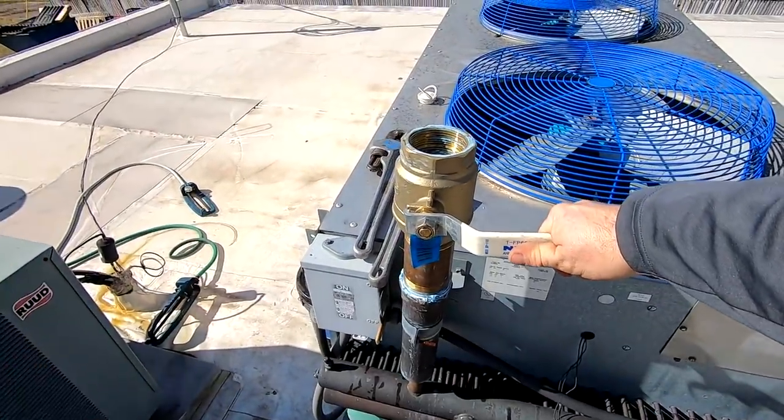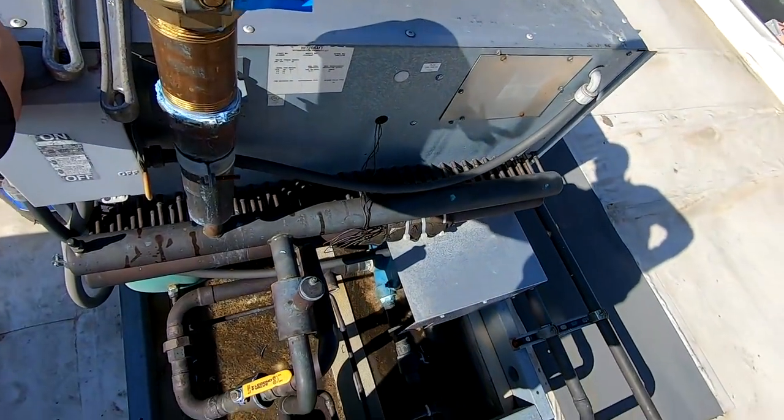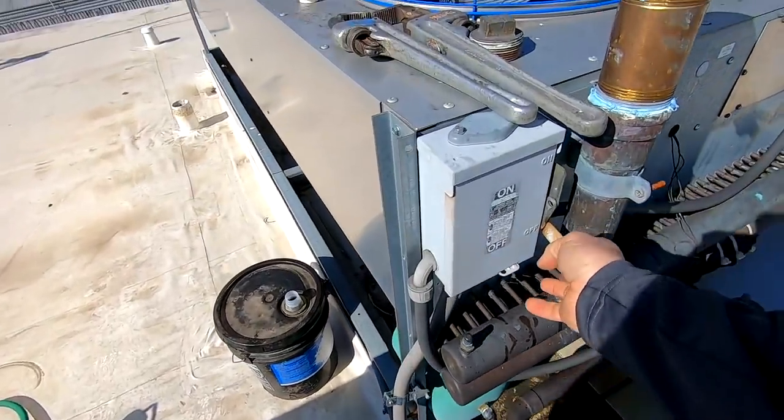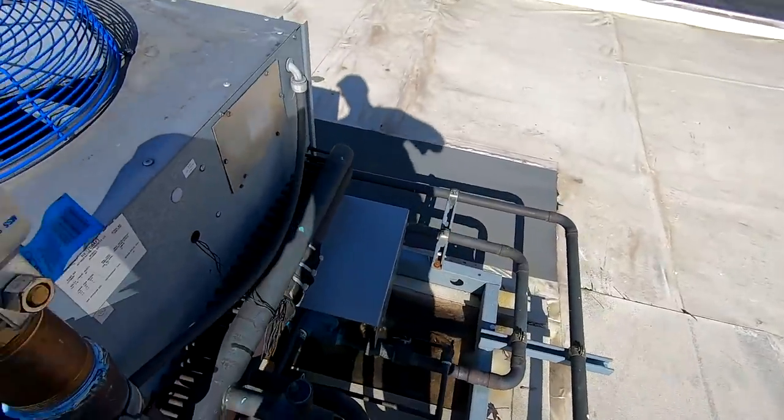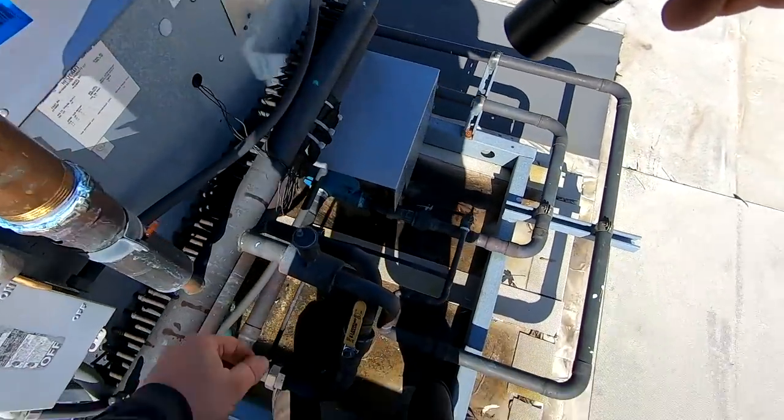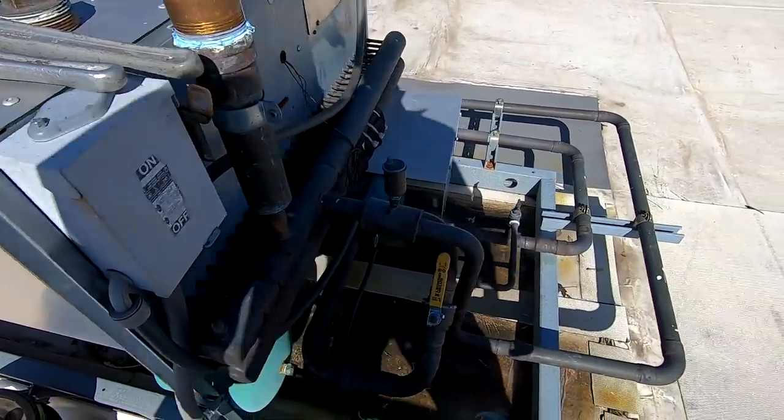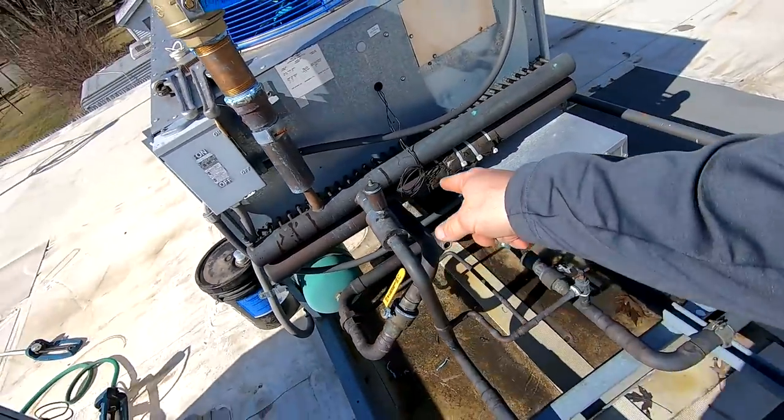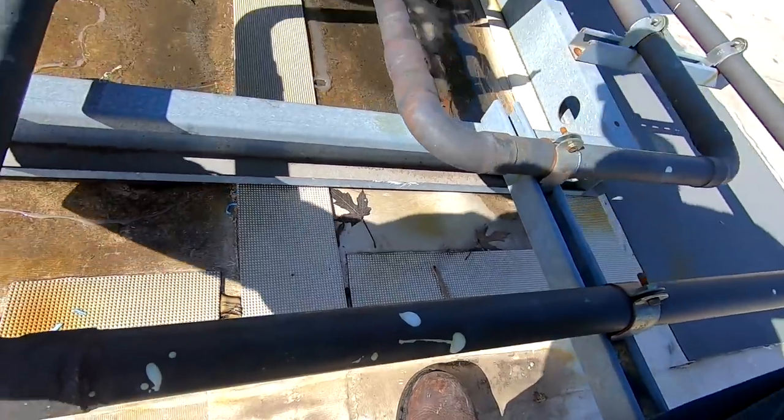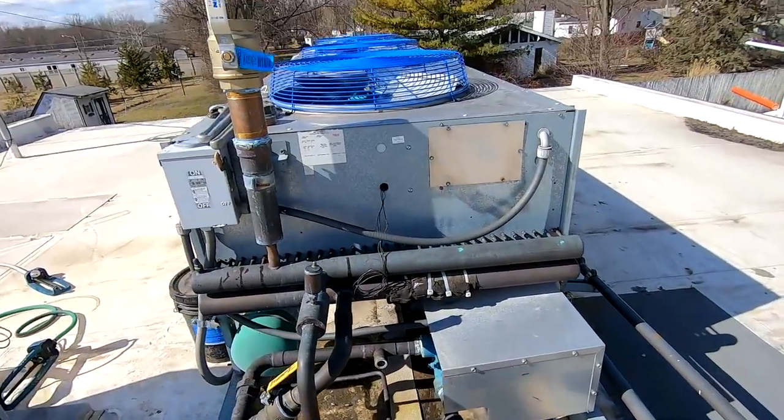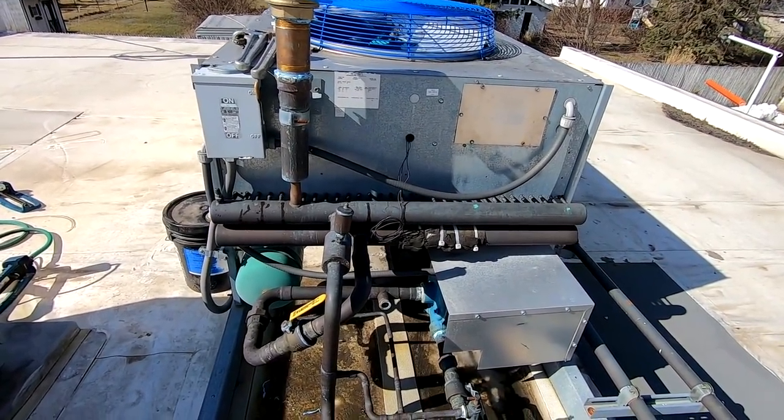Okay, hopefully we don't get shot in the face. Hell yeah. So got some there. Let's see how the pump looks, see if it's circulating. Close that back down. I'm going to let this circulate for a bit. It pulls off the bottom header there. I want to make sure that we got solid stream there so we're not running the pump dry. So I'm going to go downstairs, I'm going to get a sample of it now that's all mixed together and see what my strength is at.